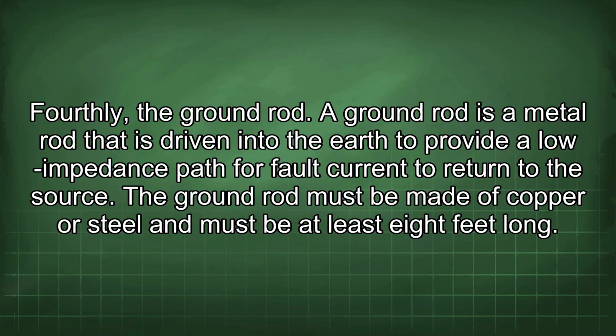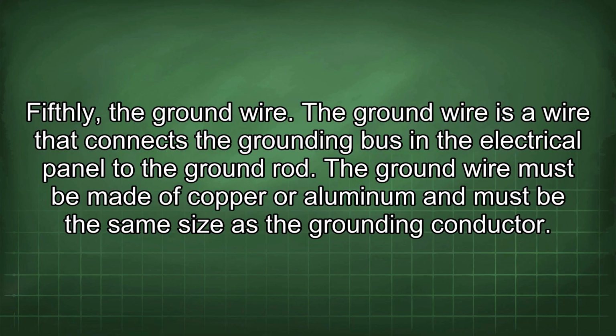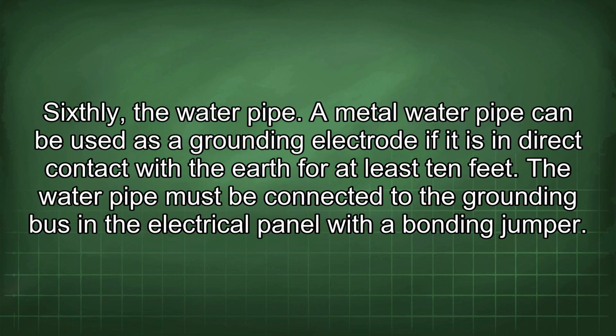The ground rod must be made of copper or steel and must be at least 8 feet long. Fifthly, the ground wire. The ground wire is a wire that connects the grounding bus in the electrical panel to the ground rod. The ground wire must be made of copper or aluminum and must be the same size as the grounding conductor. Sixthly, the water pipe.